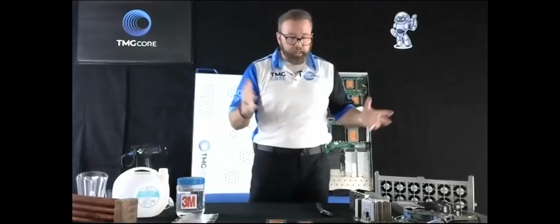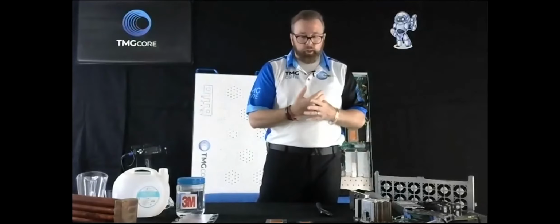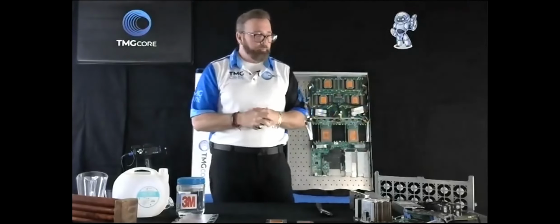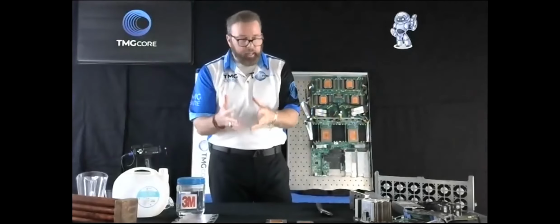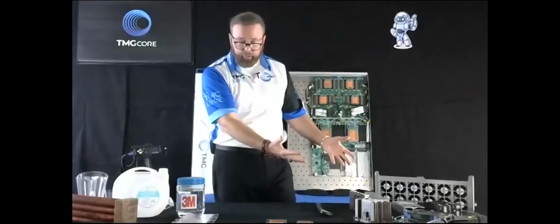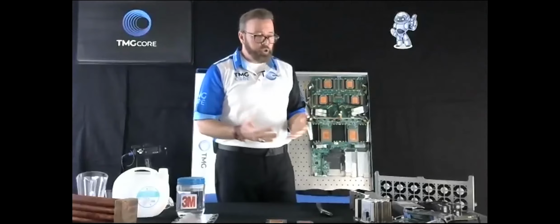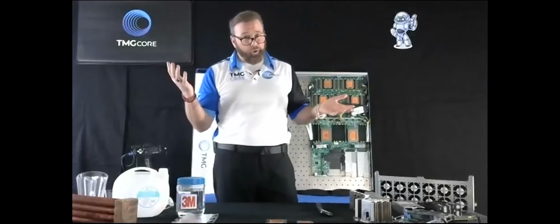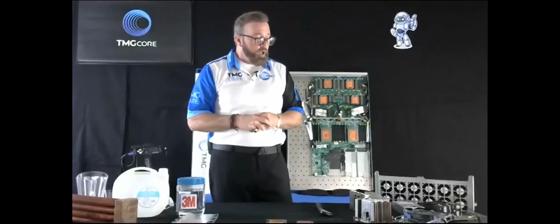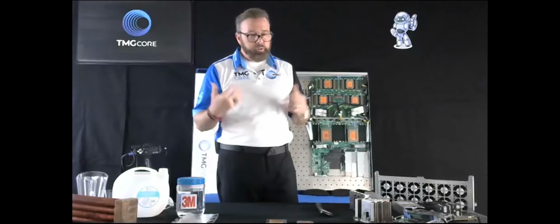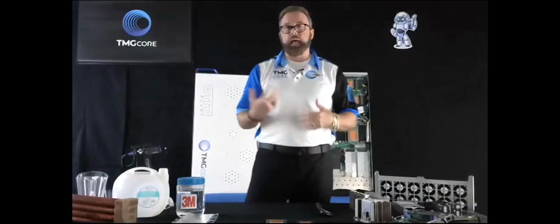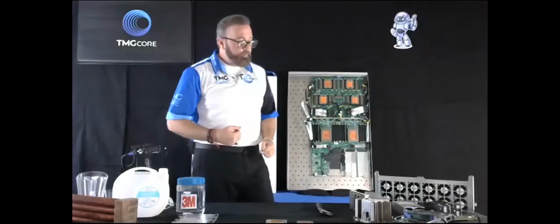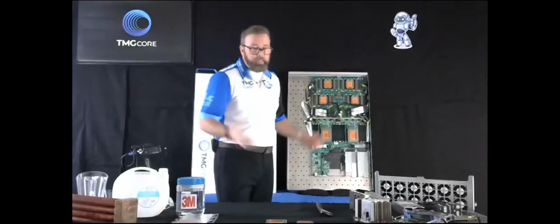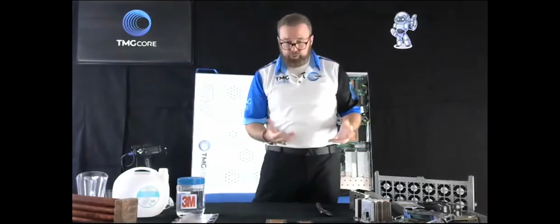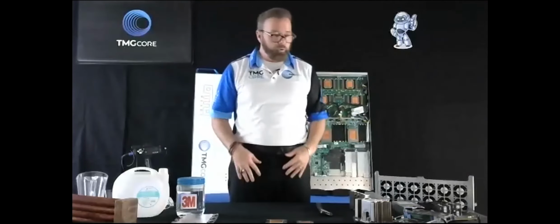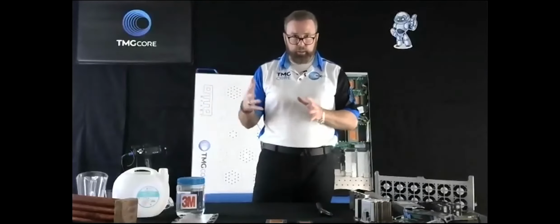Consider cost, size, efficiencies, how much energy you're using, and what's going into your workload, the actual compute versus what's going into the cooling application. In some cases, you could be using 25% or more, and 40% in some cases, of your electricity towards cooling versus the compute. The more we can drive to the compute in a smaller amount of space at higher efficiencies, the better off we are. That's what we're going to talk about.